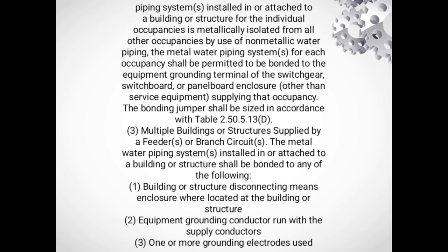Where the piping system installed in or attached to a building or structure for the individual occupancies is metallically isolated from all other occupancies by use of non-metal water piping, the metal water piping system for each occupancy shall be permitted to be bonded to the equipment grounding terminal of the switchgear, switchboard, or panelboard enclosure. Other than service equipment supplying that occupancy, the bonding jumper shall be sized in accordance with Table 2.50.5.13D.